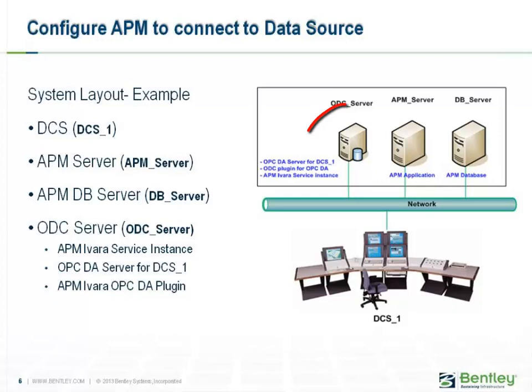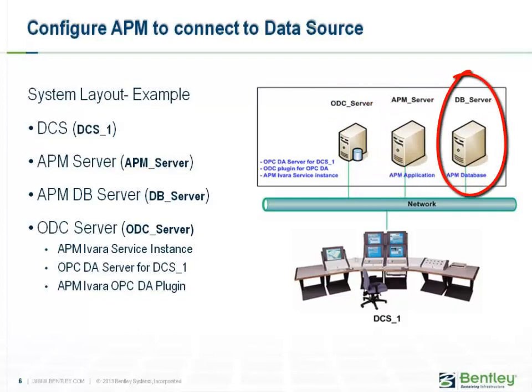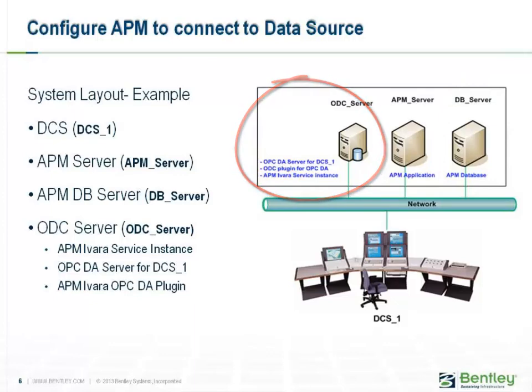Let's assume we need to connect a Distributed Control System (DCS) called DCS-1 to an APM system with the following layout: one machine called DB_server dedicated to hold and manage the APM database, and one machine called ODC_server dedicated to handle Online Data Collection (ODC), with the following applications running on it: an OPC DA server compatible with the DCS, an OPC DA plugin, and an APM service instance. Note that this is one possible layout — other layouts are also possible, and you should refer to your actual system layout when configuring your own APM system.